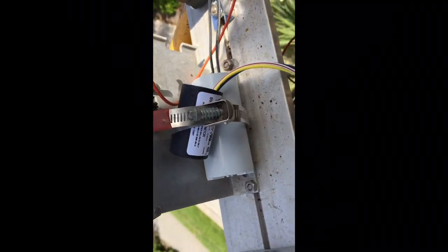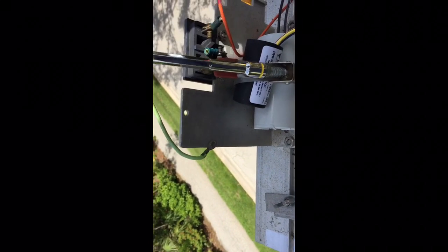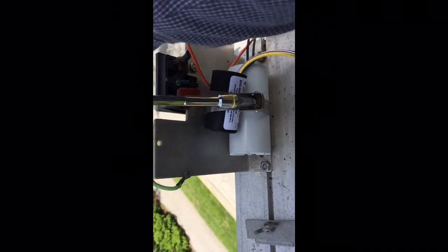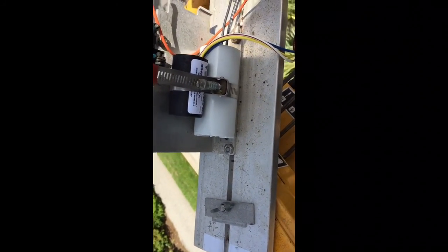See this design — this plug is supposed to be a disconnect, and you're supposed to hook the hots up here. Well, whoever put the strip right here where they can touch... this is so asinine, it's like a fence. Get it nice and tight, don't overdo it because you can break the plastic — just enough to where they don't move. We're not using that plug because it just causes problems.